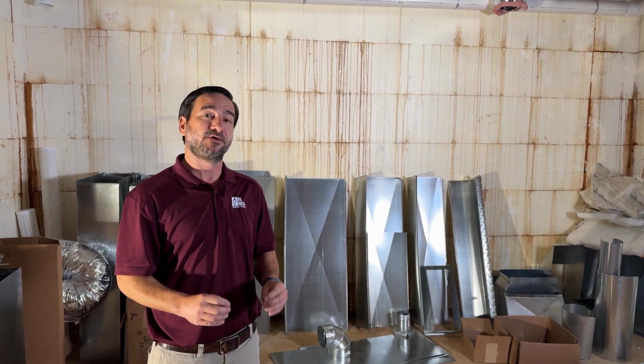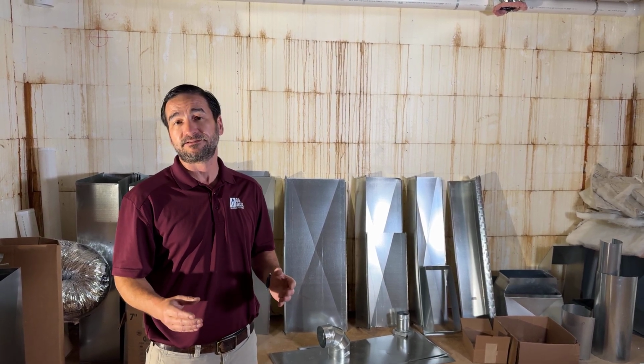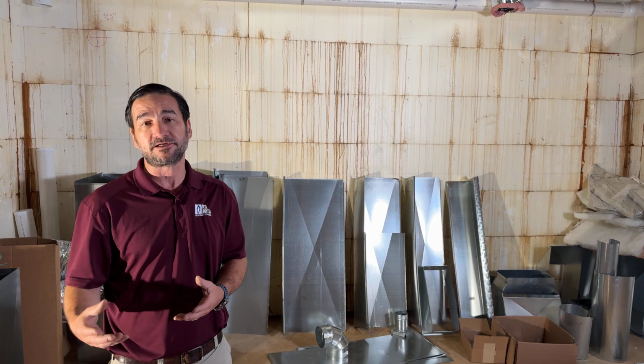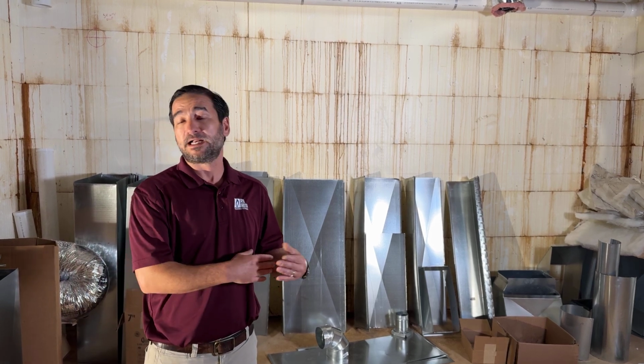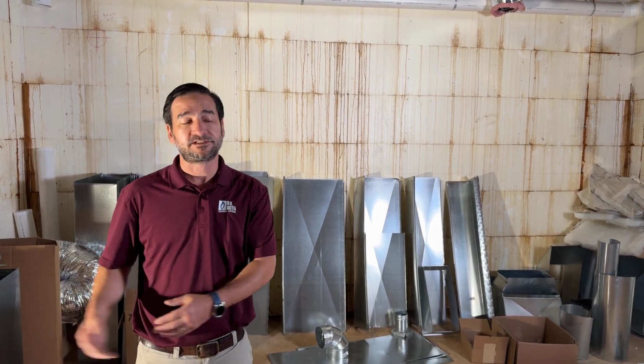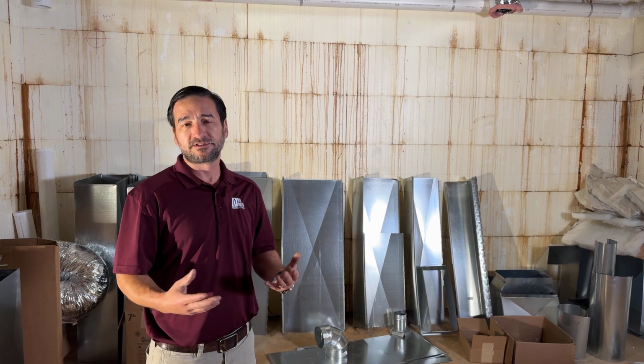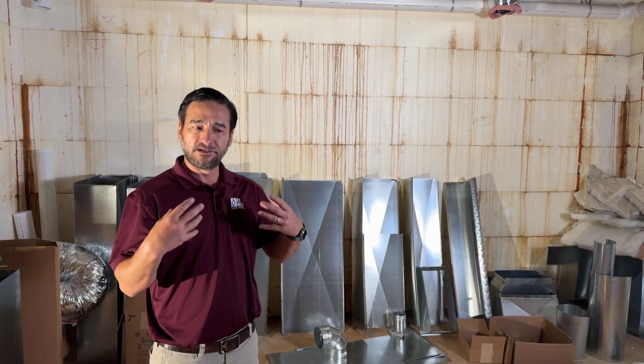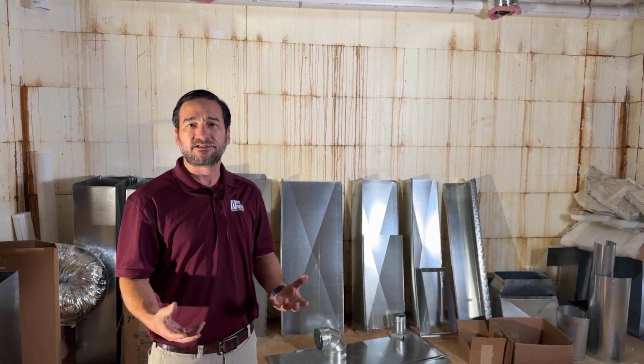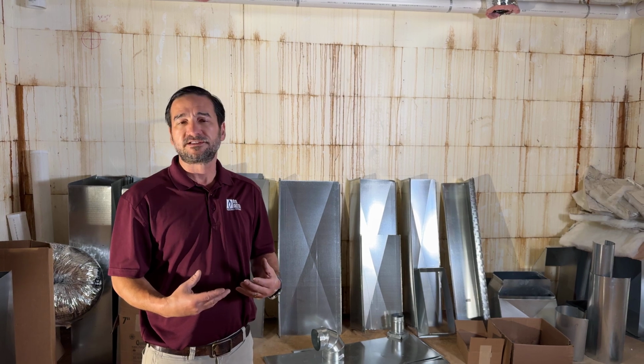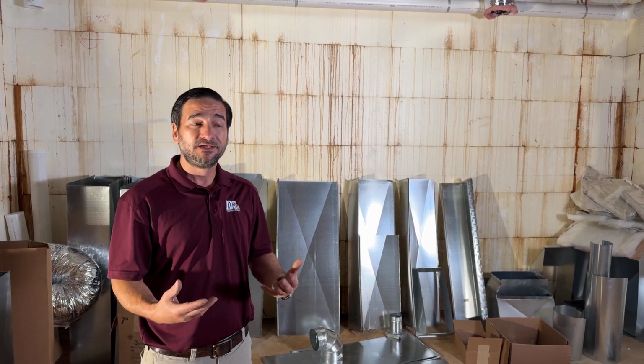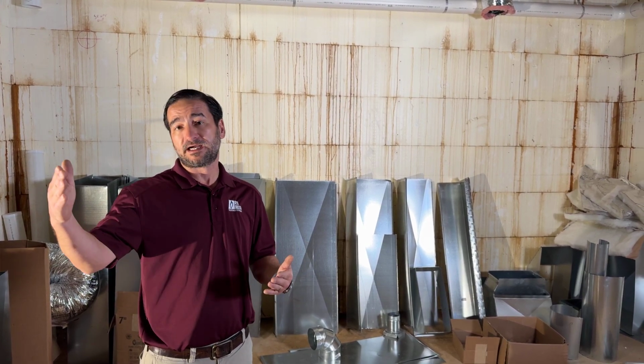And if you are going to do a zone system, I think it's a necessity. When homeowners are talking zoning, I always tell them I would not go any lower than this. So a multi-stage unit. The furnace is much the same thing. The furnace would be, first stage is roughly 60-65% of the capacity. You'll find it runs there probably 75% of the time. And then when it gets really cold, it kicks up into high fire.